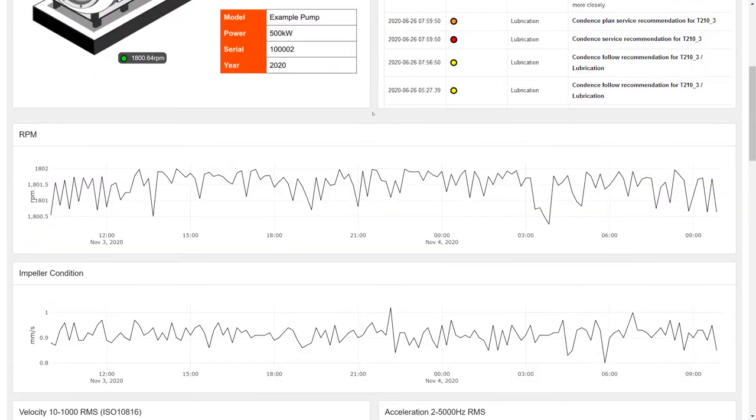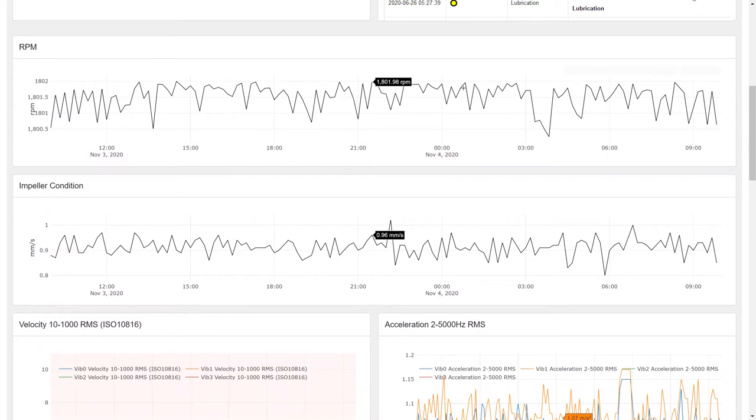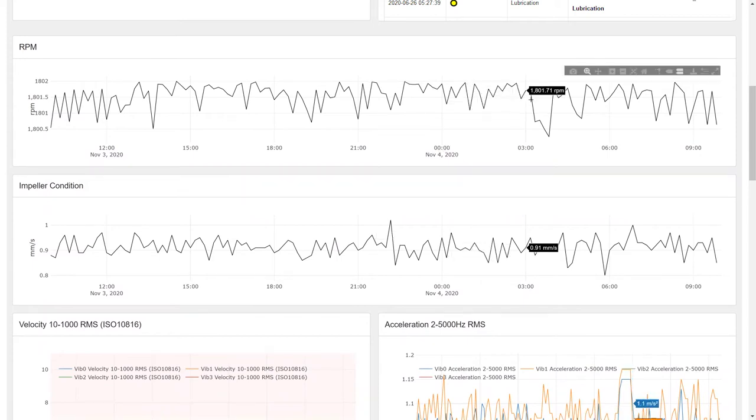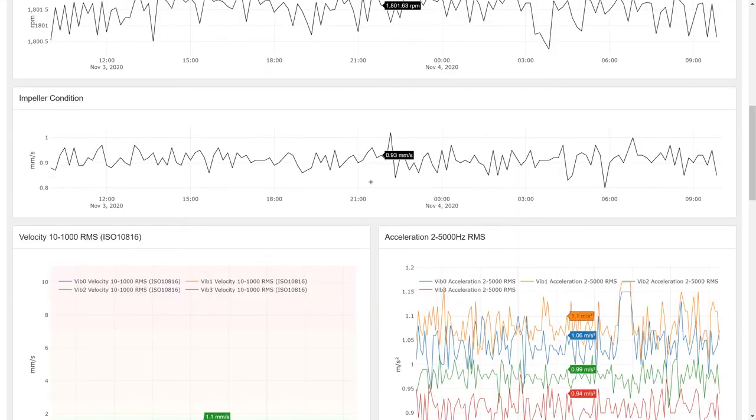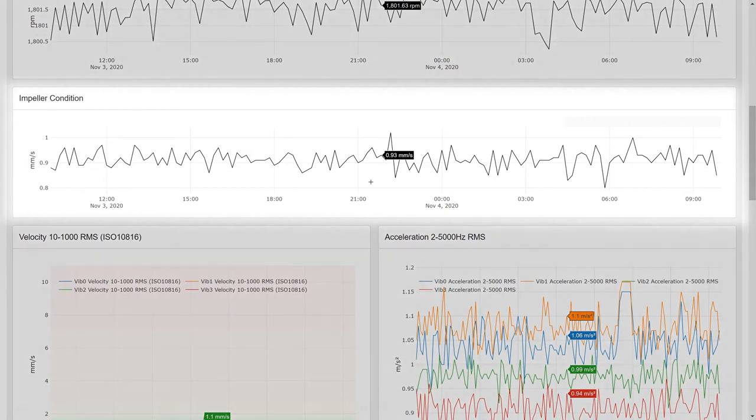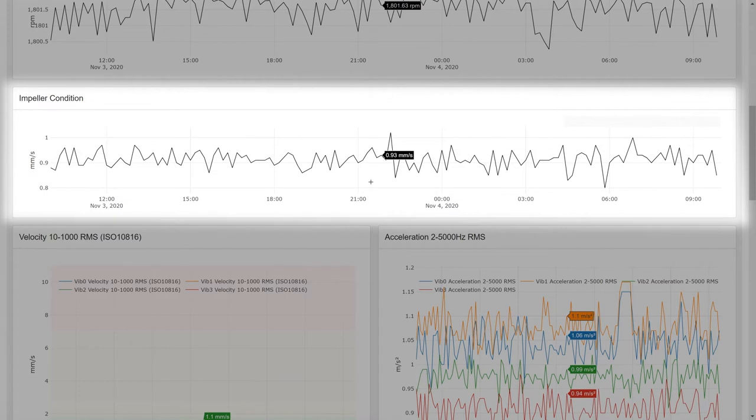Next is the trend views. In this monitoring concept, we've brought first a look into the pump's vane pass metric. Changes in the amplitude for this metric indicates, for example, if debris has damaged the impeller or if there is a dirt buildup occurring. Accidental or slowly developing faults can be detected early and proper measures taken with a schedule of your choosing.